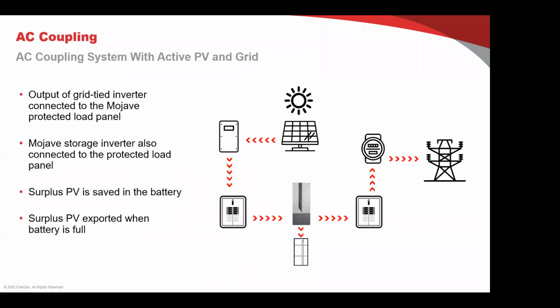Okay, so when we do an AC coupling system, we take some of those loads that are critical, we move them to a protected load center, then we insert the inverter in series here. This is just a power flow diagram. These aren't actually hooked in series. The output of our inverter and this load panel are connected in parallel, even though the power flow looks like it's in series.